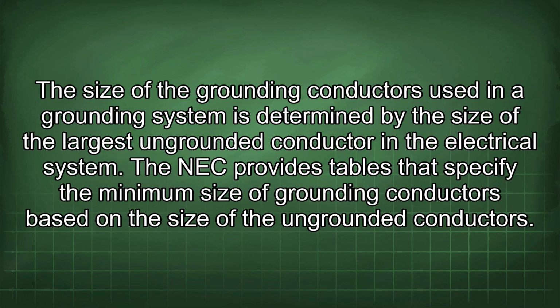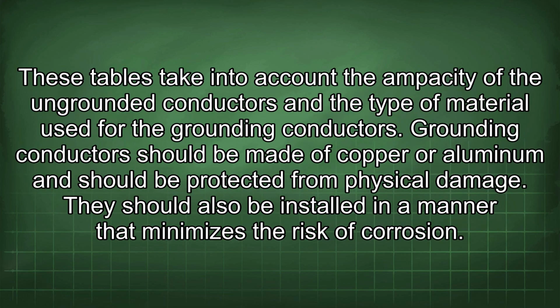The size of the grounding conductors used in a grounding system is determined by the size of the largest ungrounded conductor in the electrical system. The NEC provides tables that specify the minimum size of grounding conductors based on the size of the ungrounded conductors. These tables take into account the ampacity of the ungrounded conductors and the type of material used for the grounding conductors. Grounding conductors should be made of copper or aluminum and should be protected from physical damage. They should also be installed in a manner that minimizes the risk of corrosion.